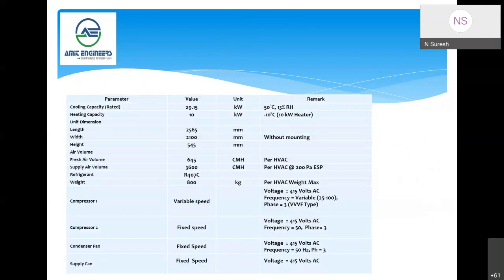Okay, so when we talk about the capacity of the unit we are going to give for this project, this is somewhere around 8 TR, that is approximately 29.15 kilowatt at 50-degree ambient. Normally in Indian Railway, whatever products we are giving, that is a very rugged design. At any extreme condition, the system will give the desired cooling capacity to maintain the temperature and humidity. This system is designed for 50-degree and 13% RH, that is 25-degree wet bulb temperature, and approximately 10 kilowatt, less than 10 kilowatt heaters are available that will work whenever the temperature goes below 18-degree.